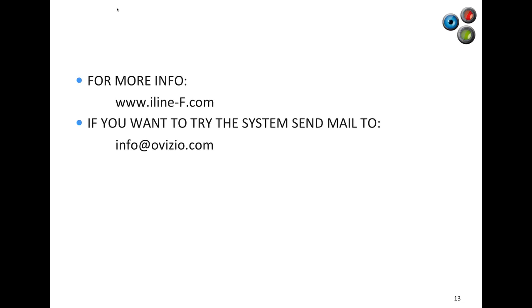The advantage is that this is an inline method, so you can mount a probe directly into the bioreactor, sterilize it in line with the process or with the bioreactor in the autoclave. So it's very easy, but you are using capacitance of a cell. In theory, you're measuring all the viable cells, but you are not measuring cell numbers or concentrations directly. What you get is a reading on cell volume, total cell volume, that is in a certain space close to the probe.